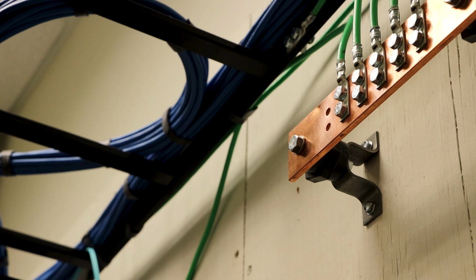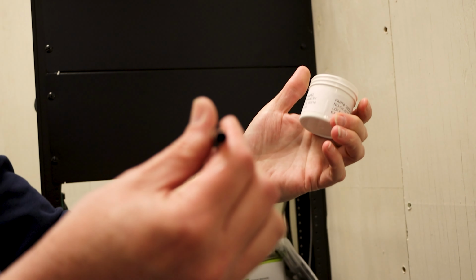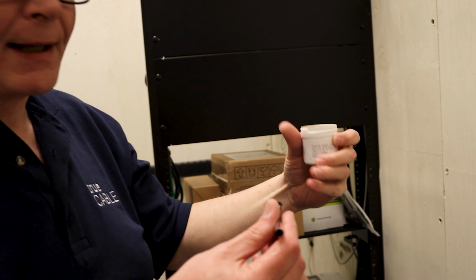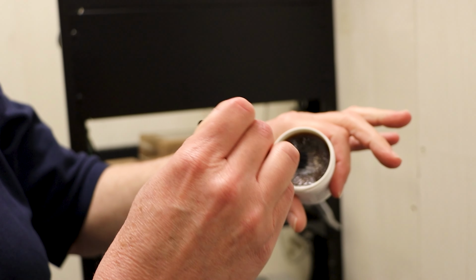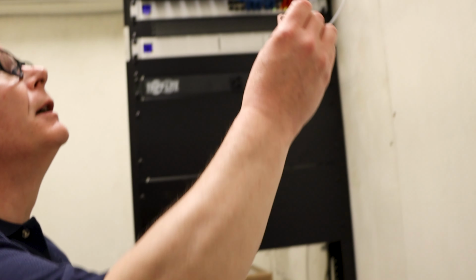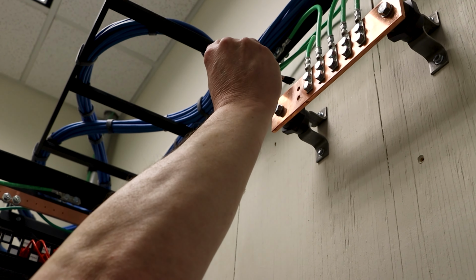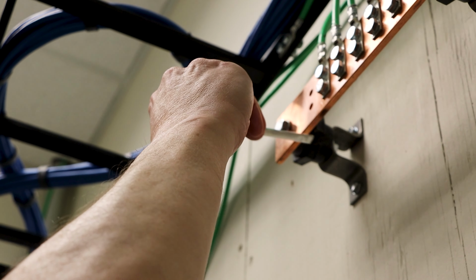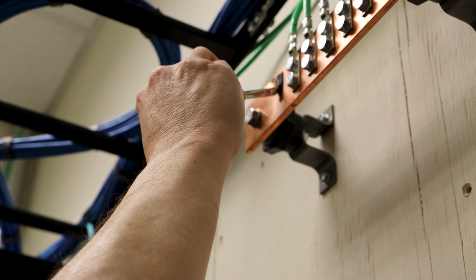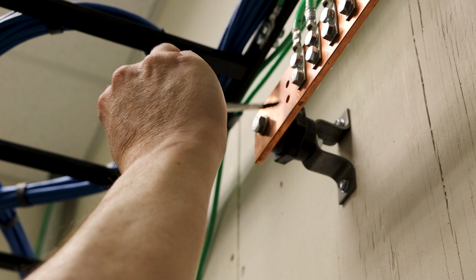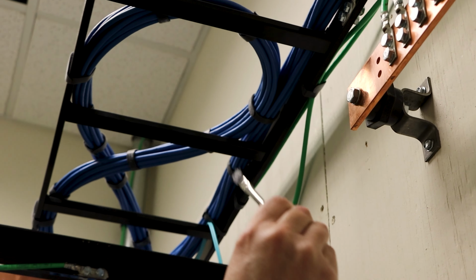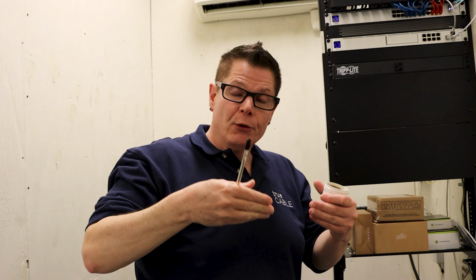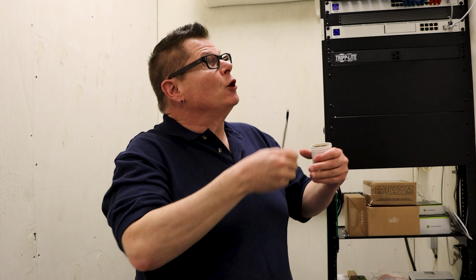After that, you then take your no oxidation paste, grease. This is made by Sanchem. It's called No-Ox, it's very popular. And then you apply a very thin coat of this grease to where the lug is going to bolt down. And you don't have to go crazy with it. You're just looking to put a light coat on there so that the copper does not oxidize any further. And at that point, you would attach your lug, which has already been crimped onto your 6 AWG bonding conductor, and then you would torque it down to the proper torque specifications that's called for by the instruction hardware that came with the bus bar.